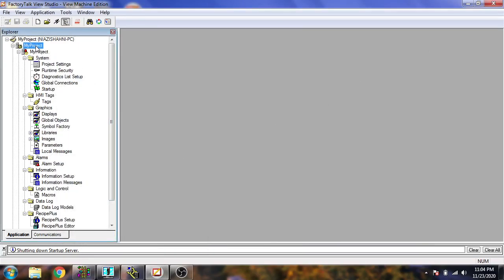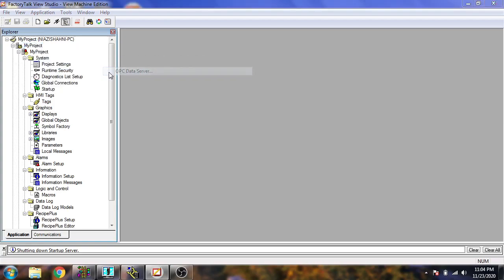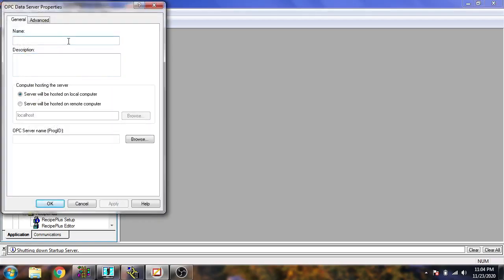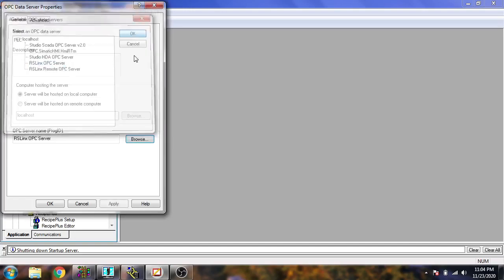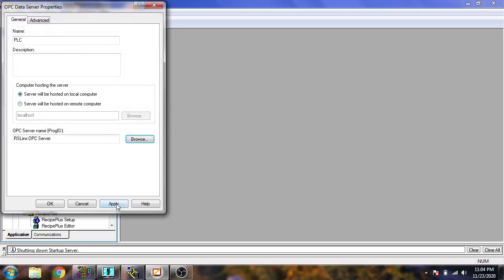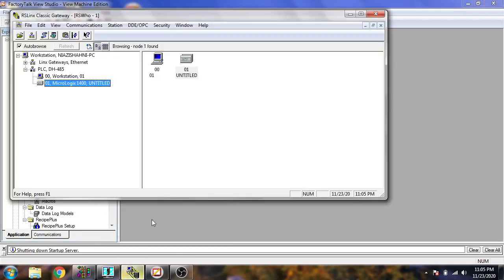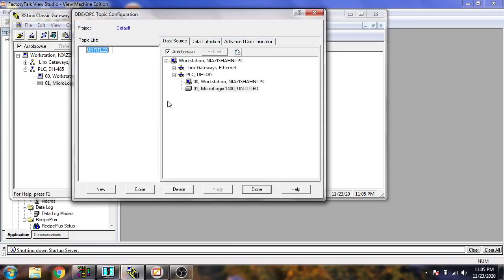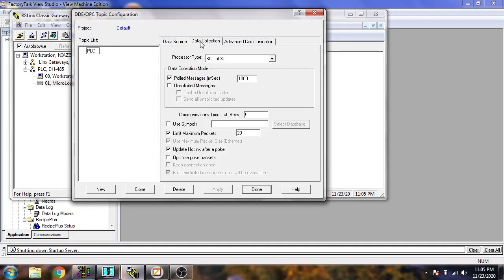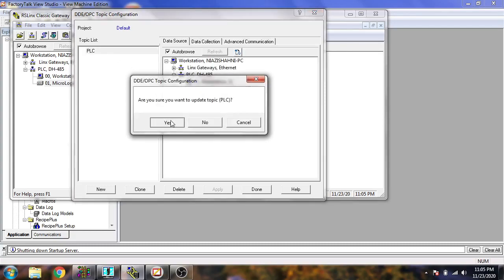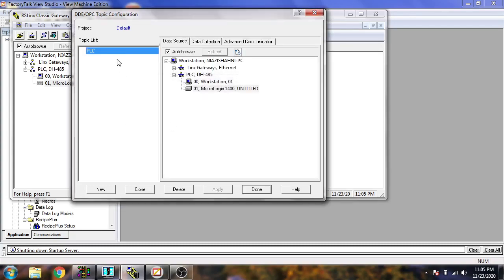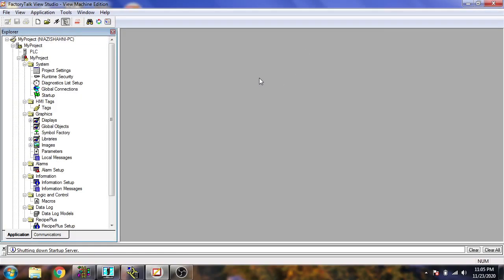I'm going to show you how we create the project. I'm going to my project, add a new server, an OPC data server. I'm just going to name it PLC. I'm going to browse it and select an RSLinx OPC server. Okay, apply and okay. Now our RSLinx OPC connection and create a new configuration and just name it also PLC and see that our setting is correct. Now I'm just going to select our PLC, update that, I'm going to be done with that. Now our OPC connection has been created.